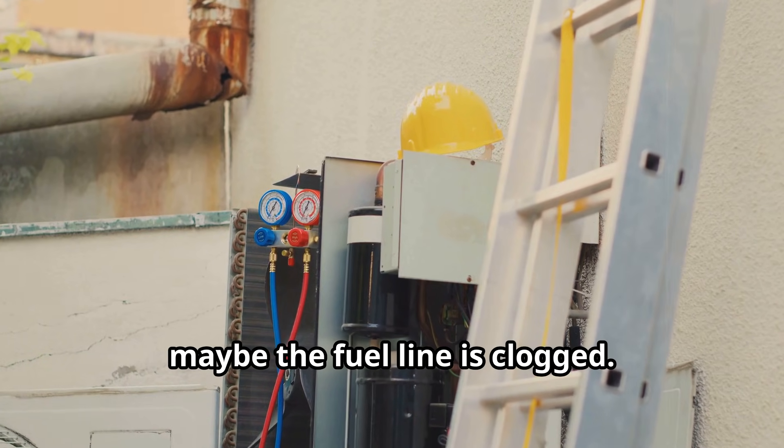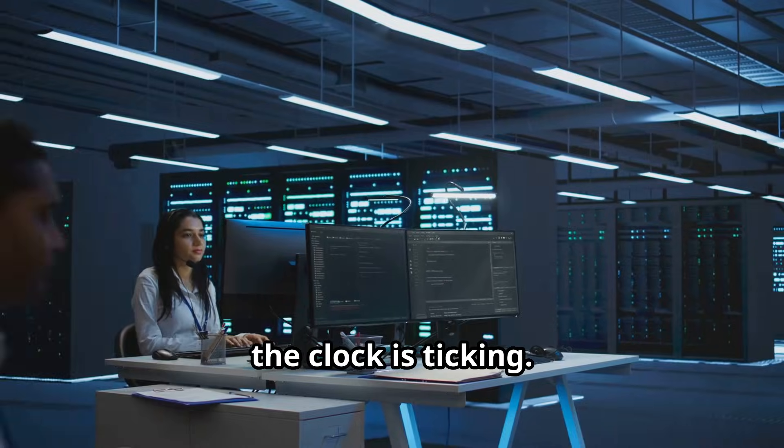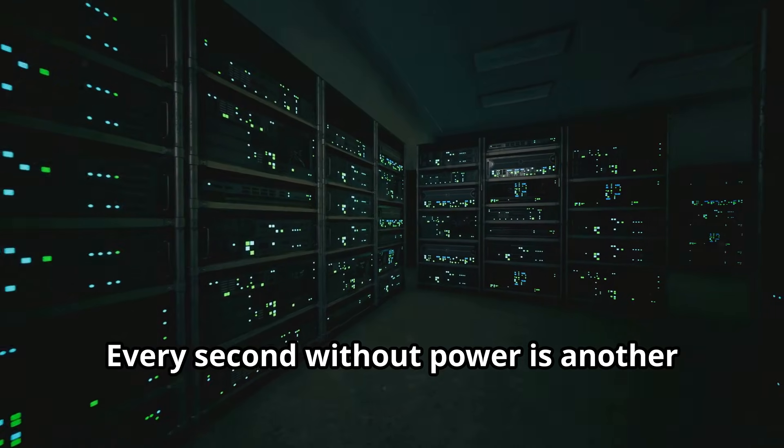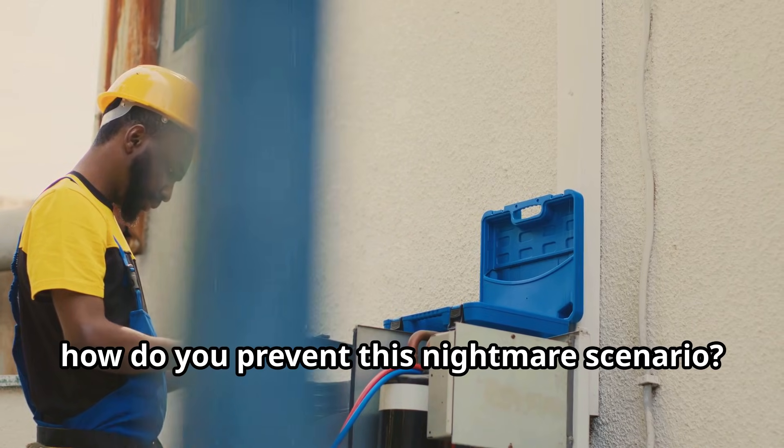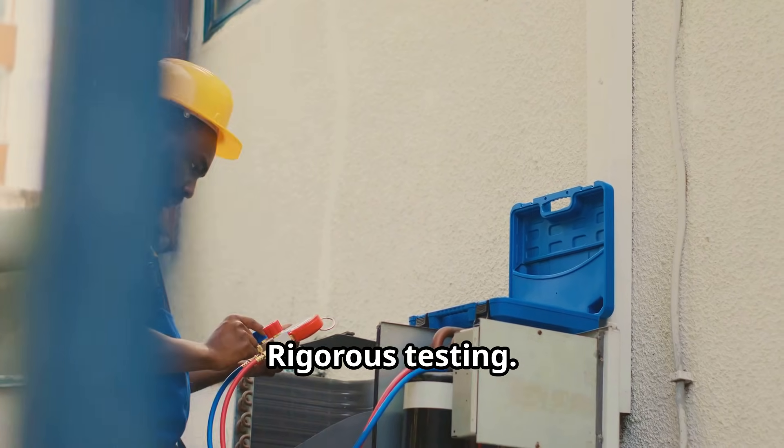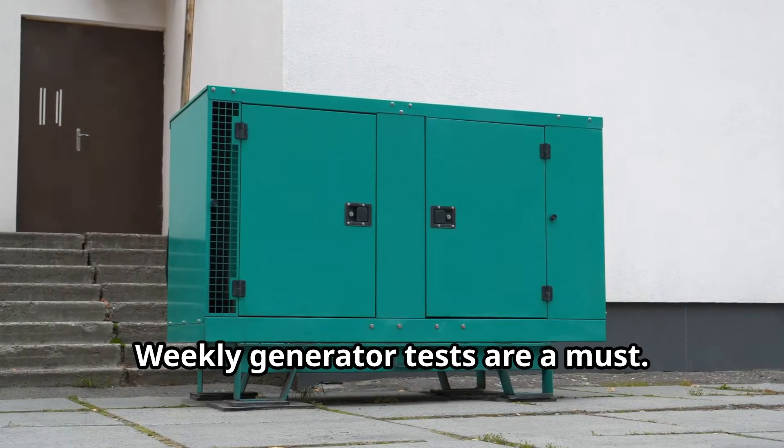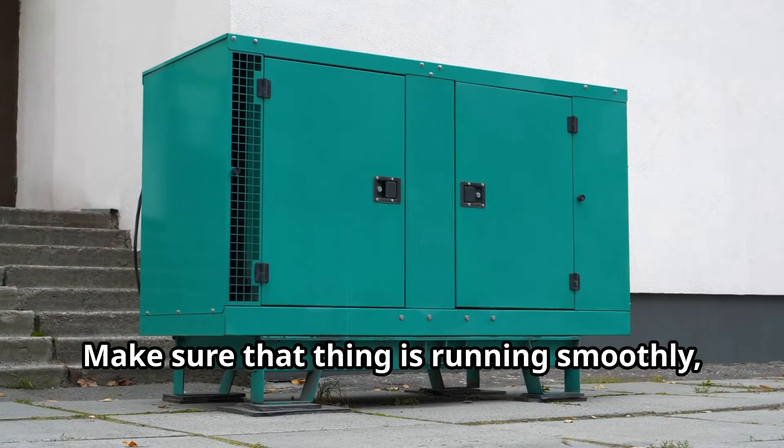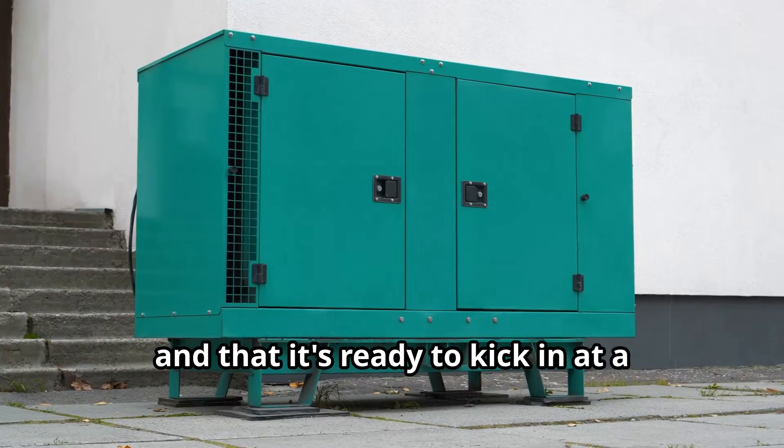Whatever the reason, the clock is ticking. Every second without power is another nail in the coffin of your data center. So how do you prevent this nightmare scenario? Rigorous testing. Weekly generator tests are a must. Make sure that thing is running smoothly, that the fuel is flowing, and that it's ready to kick in at a moment's notice.